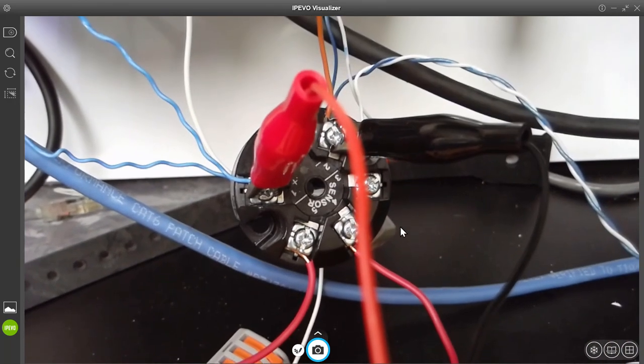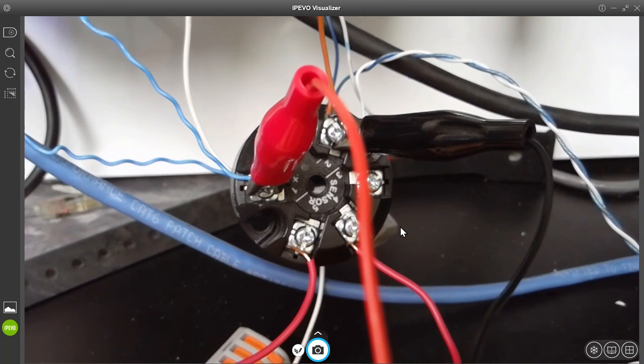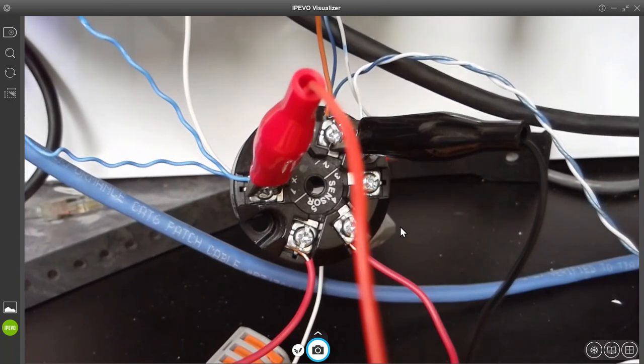One thing I would caution you about is this will load the circuit. So we are going to load our circuit. When you have your USB configurator hooked up, you will not display the correct data on the PLC or runtime HMI. Once you've programmed it, that is all we do. Disconnect it. You should only have to program it during installation, or if you find one that hasn't been programmed previously, which after the first round of calibrations, they should all be programmed.